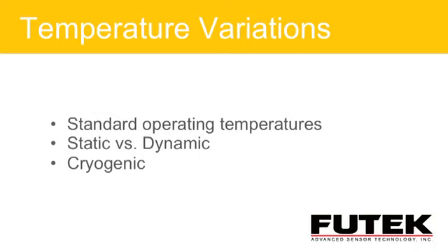You can go outside that temperature range, into cryogenics. We could push down to about negative 300 degrees F, or on the high temperature side, right around 500 degrees Fahrenheit, which is the upper limit on most of the bonded foil strain gauges we utilize. With cryogenic and high temperature, you have to pay real close attention - especially the sensor designer - to the components utilized, glass transition changes. There's a lot that can happen in these environments.